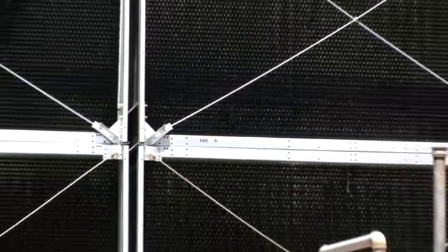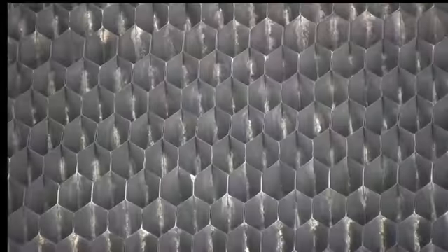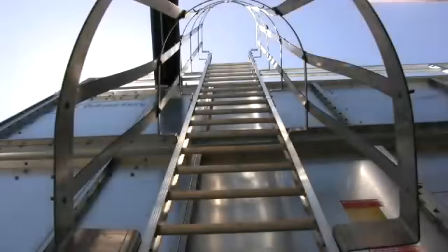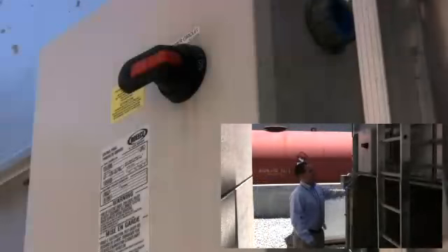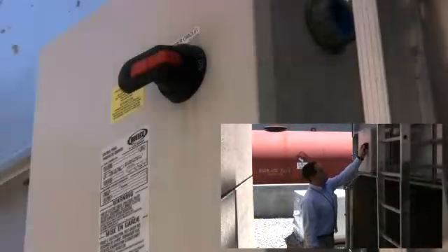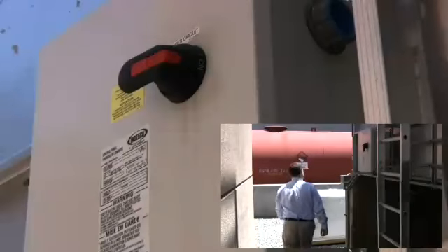Collection of samples from a cooling tower can be hazardous, and it is recommended that several steps be taken to ensure the safety of personnel collecting these samples. Cooling towers pose the highest risk to the collector based on several factors: aerosolization of potentially contaminated water droplets, physical location and access to the cooling tower, and dangers associated with fans and other mechanical systems. To minimize these dangers, check with the appropriate personnel to gain access to the cooling tower and shut down any systems associated with the tower while sampling.